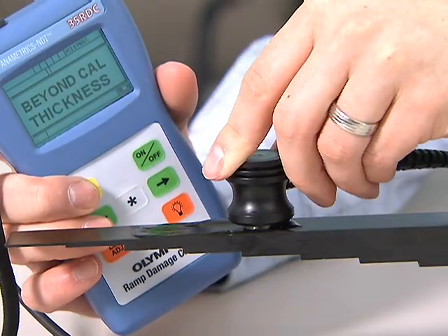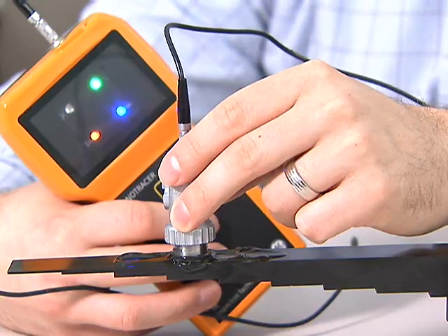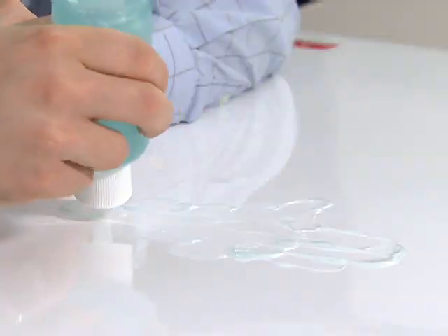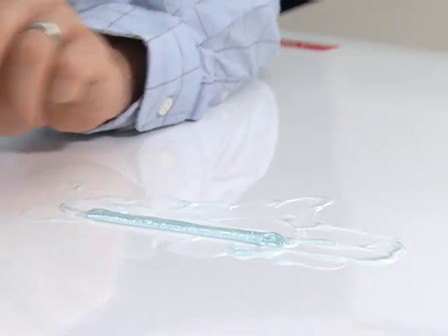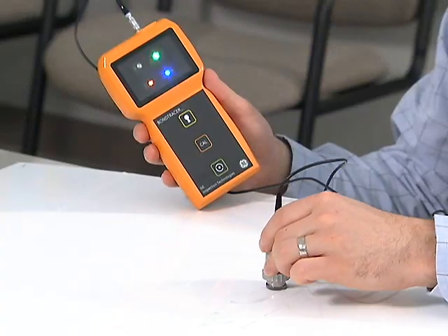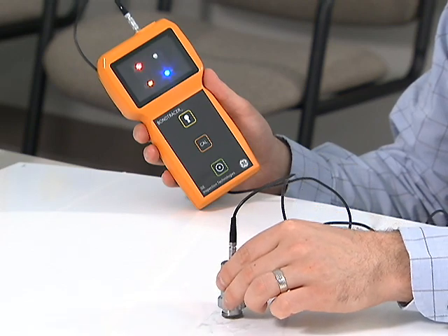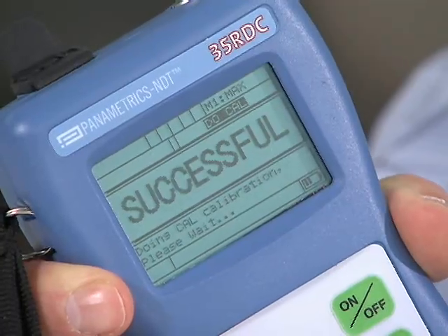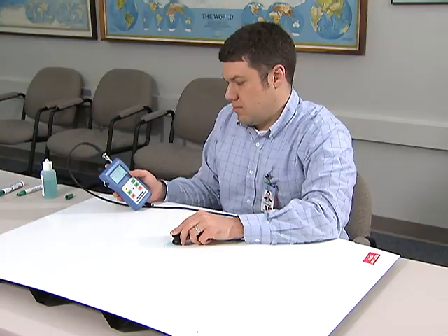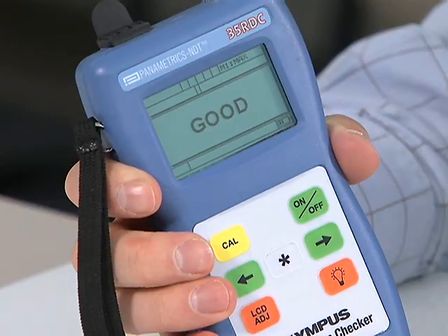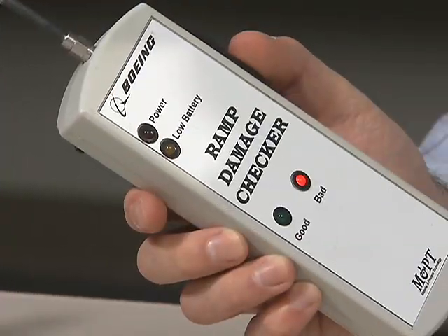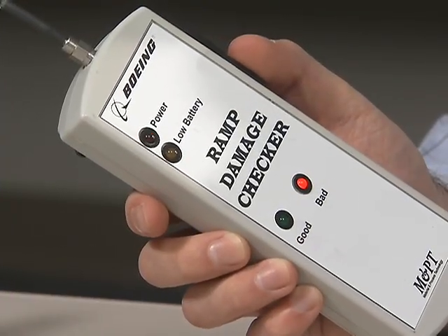Second, the instruments have different responses to thicker structure. We'll talk more about that later. Third, the Bond Tracer and the 35 RDC have differing displays for power, calibration, and battery life. There are other differences in the way these commercial versions operate. To understand the differences, it is best to read the instrument operating manual. Now that you have a basic understanding of how the RDC works, we'll go through the 6 steps in an example inspection. Visual evidence of damage causes an inspection to be initiated and is step 1.